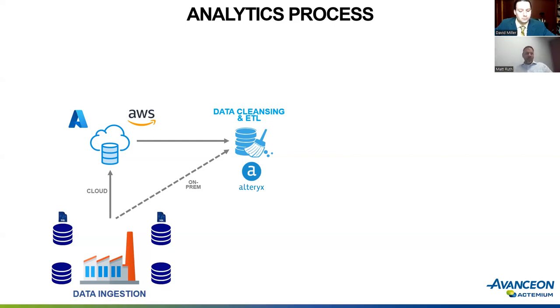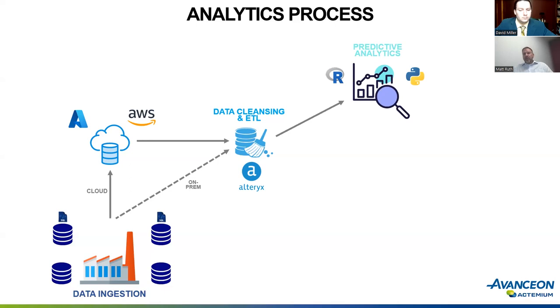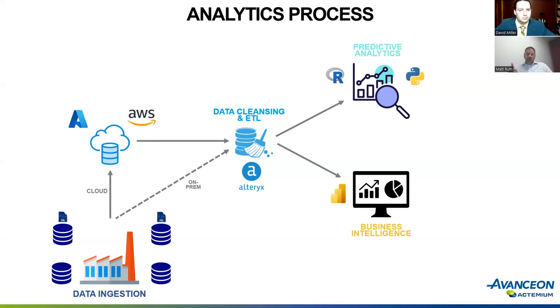There's a lot of noise in the data — times when production was technically running but shouldn't count, times a loop was in manual when it should have been in auto, or equipment was off and not receiving product. Those things you probably want to clean up to do a true good analysis. So we take it from the facility, get it into a spot where we can modify and cleanse it, and then leverage IT-oriented tools such as R and Python to perform predictive and prescriptive analytics and deeper dives. We also display that information using off-the-shelf IT solutions such as Power BI.